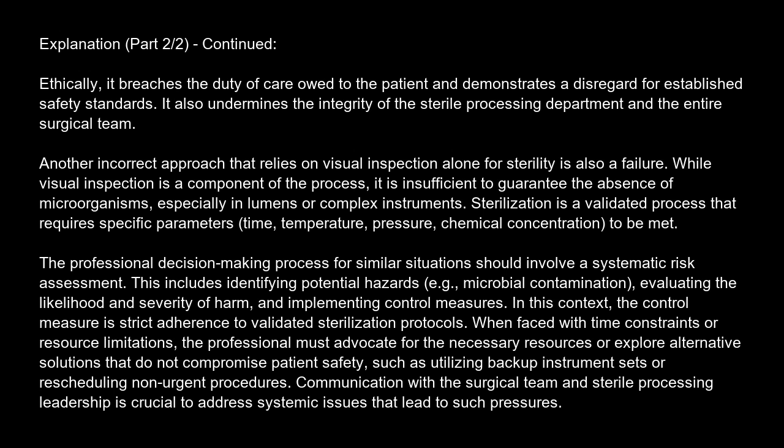Another incorrect approach that relies on visual inspection alone for sterility is also a failure. While visual inspection is a component of the process, it is insufficient to guarantee the absence of microorganisms, especially in lumens or complex instruments. Sterilization is a validated process that requires specific parameters: time, temperature, pressure, chemical concentration to be met.